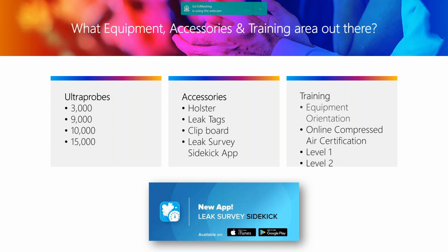Then you get into the UltraProbe 10,000 and 15,000, which opens the door to being able to record sounds, so you can play them back on an FFT or time waveform. As far as the UltraProbes go, that's what we would typically recommend right off the cuff. Again, the 3000 is very lightweight, very economical, and budget friendly for going out and doing a leak survey.